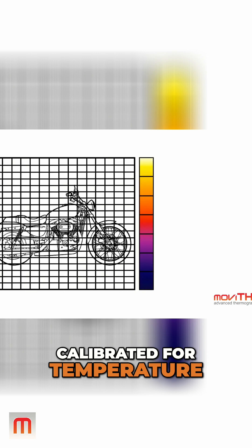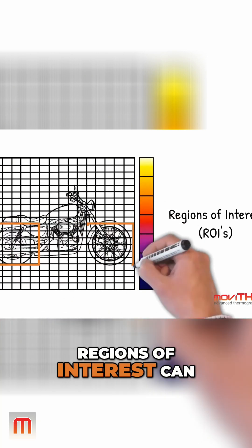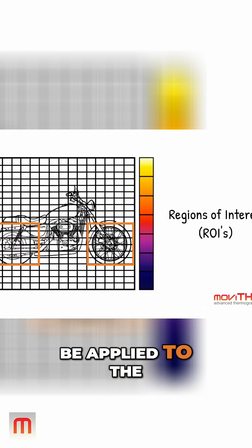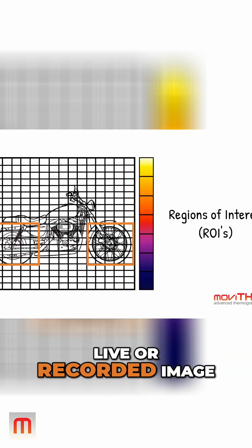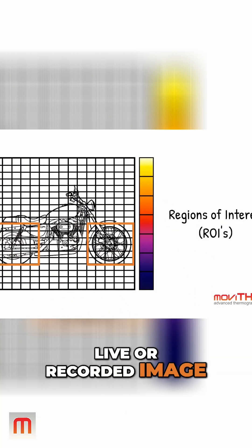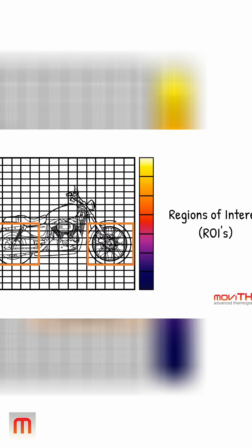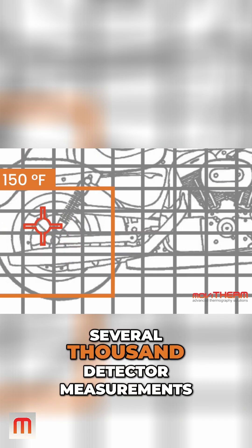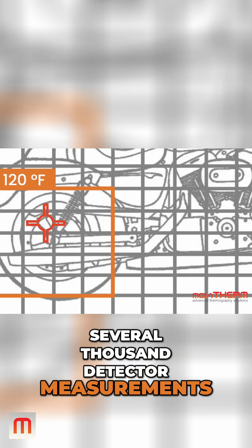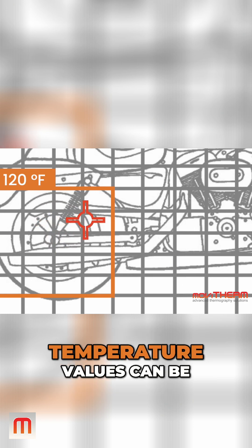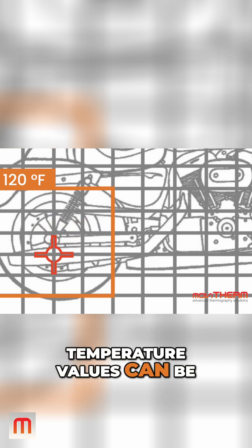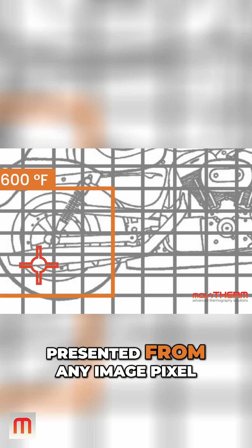If the camera is calibrated for temperature, regions of interest can be applied to the live or recorded image for temperature measurement. Because the thermal image is made up of several thousand detector measurements, temperature values can be presented from any image pixel.